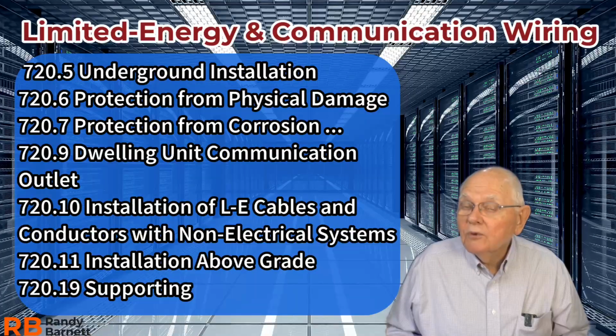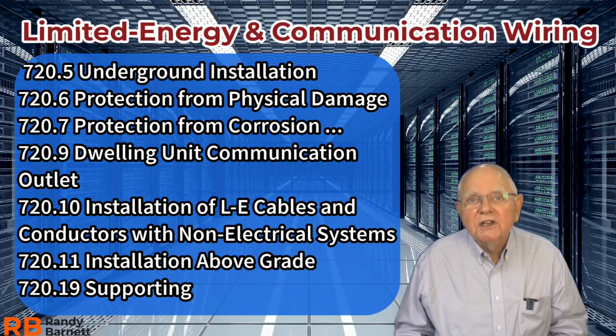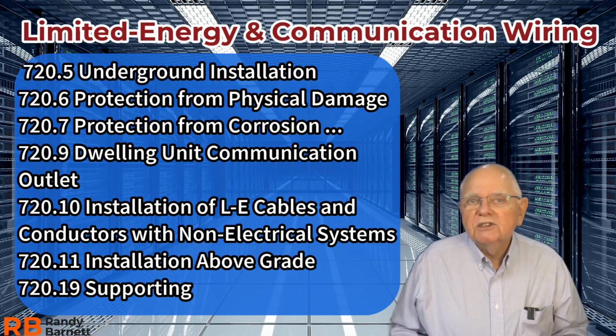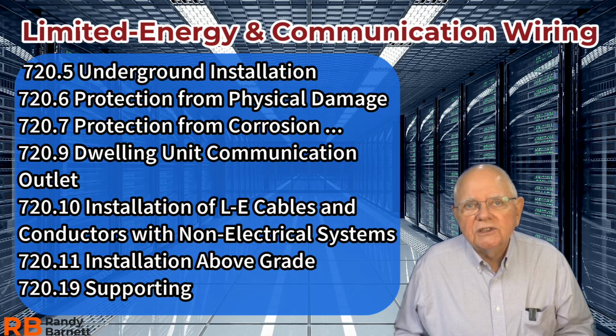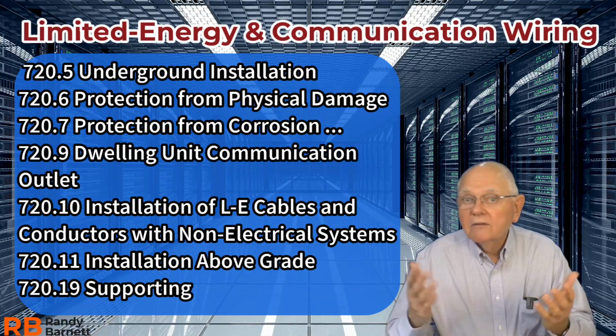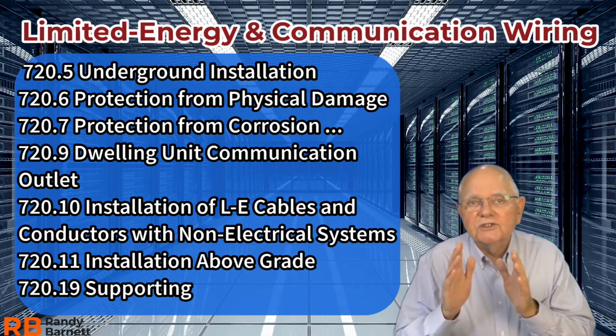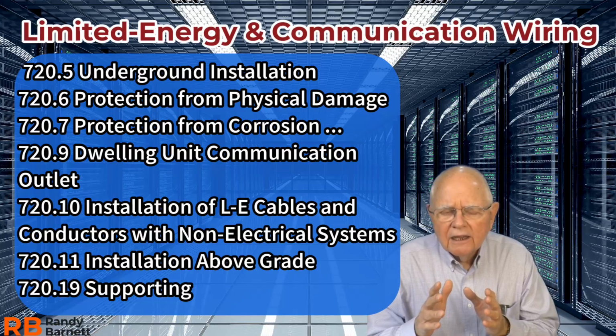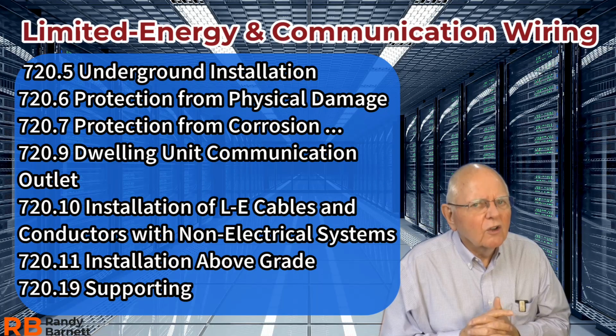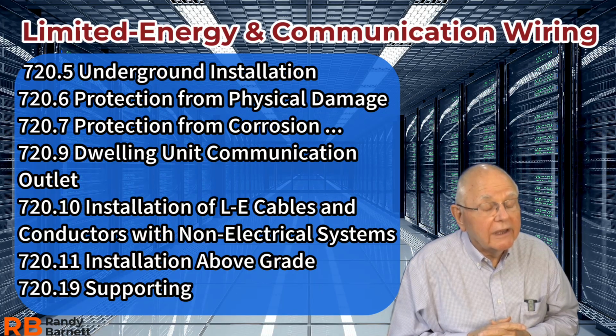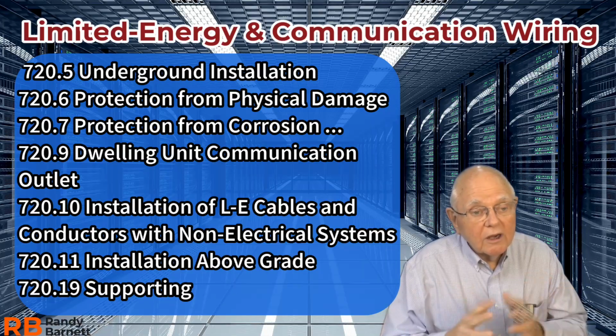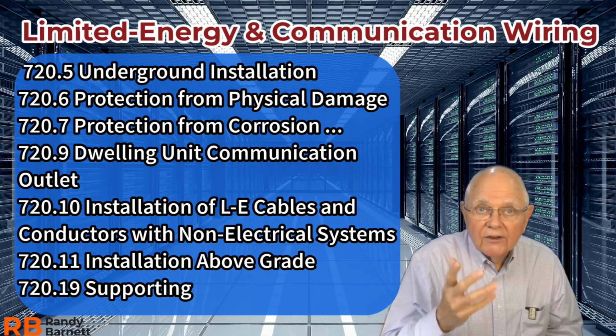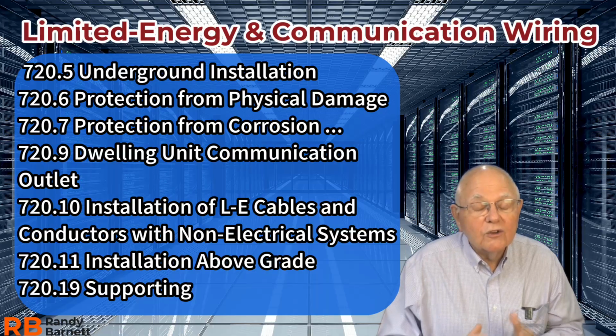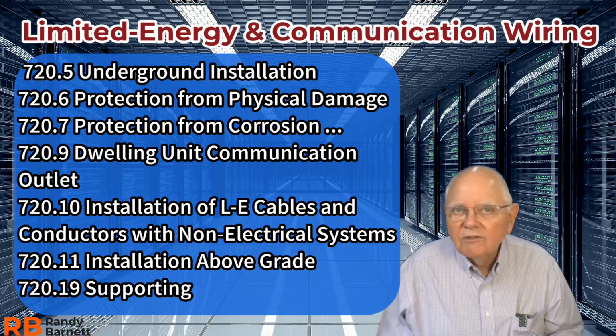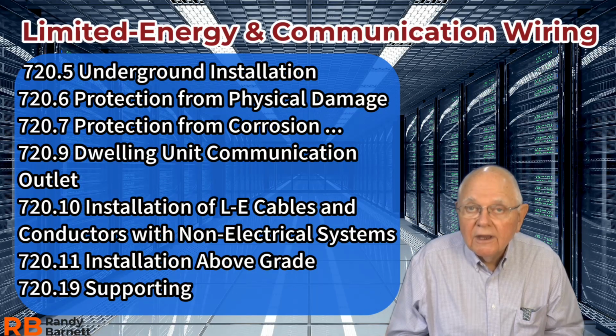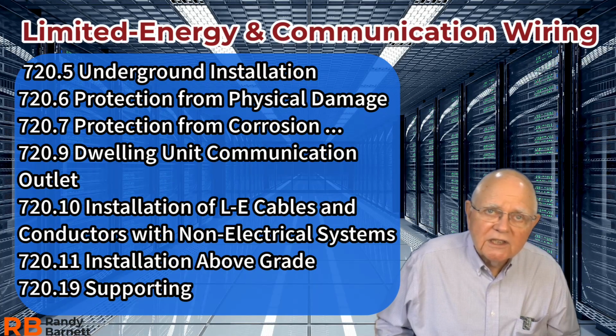720.5 gets to be pretty important. It talks about underground installations. The first subsection it talks about is wet locations. And really, by the way, as we go through Article 720, you might be saying, that sounds a lot like Article 300 back in Chapter 3. And yeah, our general wiring methods in Chapter 3 are in Article 300, and Article 300 and Article 720 closely parallel each other. But anyway, back to 720.